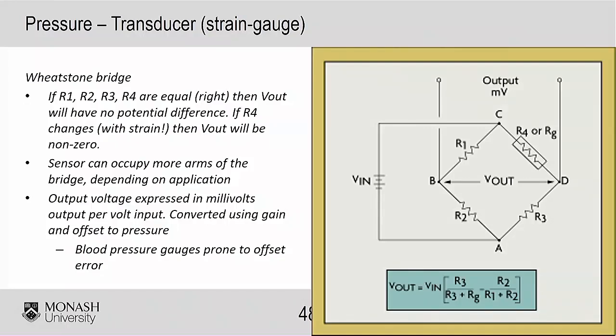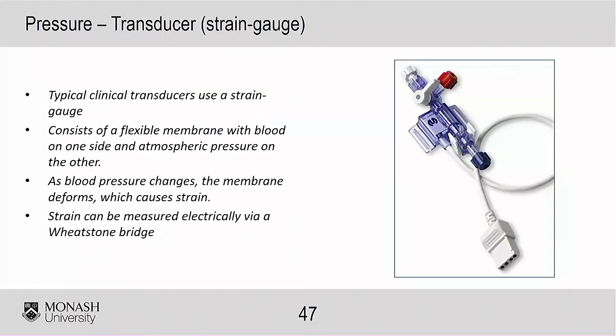So basically the answer is recalibration, regular recalibration. And we have to do that quite often. If we go back to look at this sensor again, the advantage of these sensors is this three-way tap here. As I said, the blood comes in here through there onto the membrane. Basically, whatever way this arrow is pointing is off. So what you can do is flick this arrow around to here, expose the pressure sensor to atmospheric pressure. You can re-zero the sensor because we zero to atmosphere. Then flick the tap back around to this way, and then we're measuring pressure again. Okay, so it's a very simple calibration step, just calibrating against atmosphere.